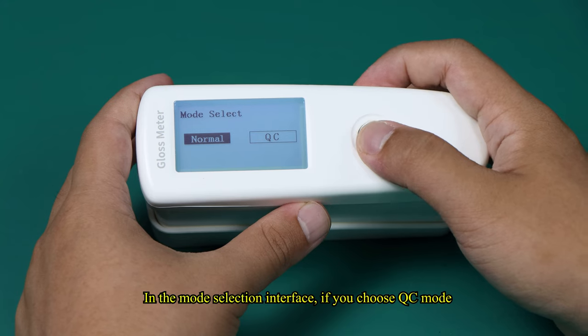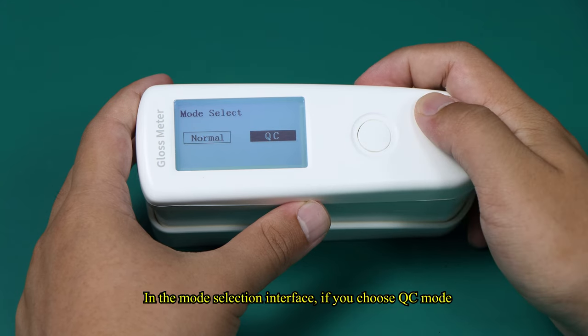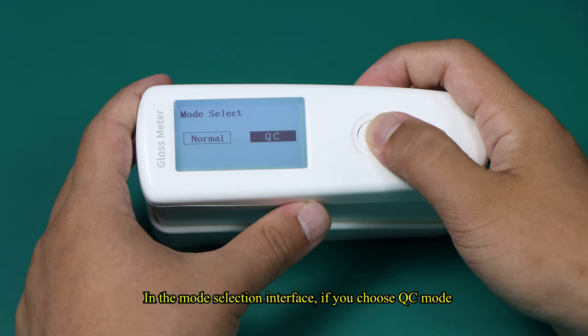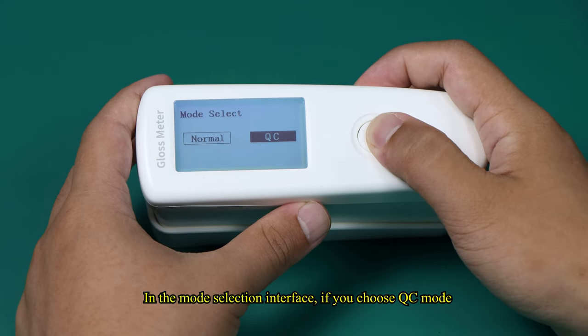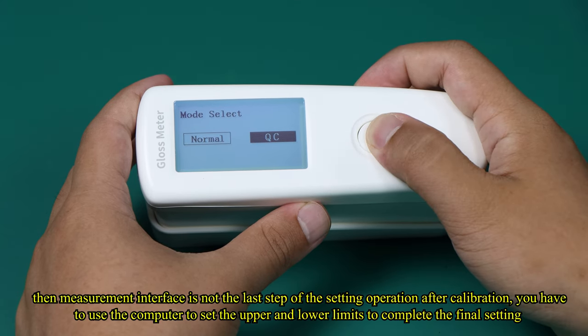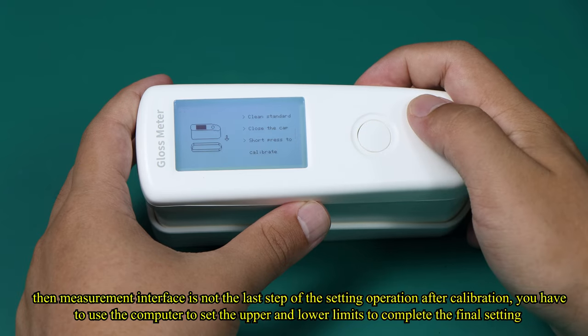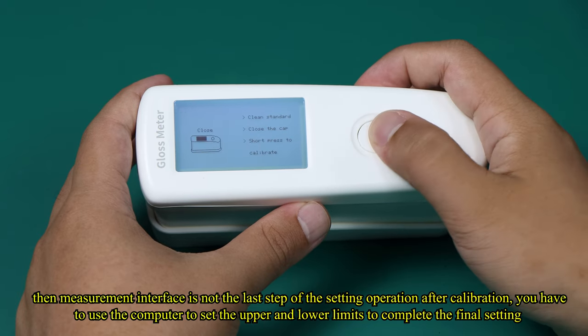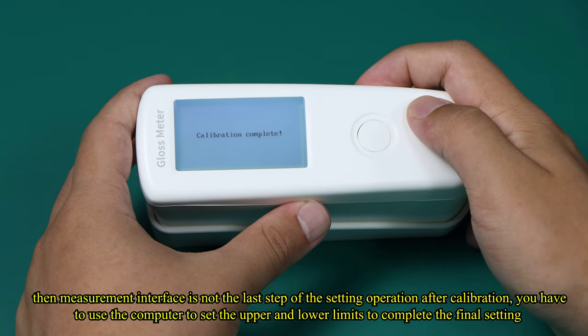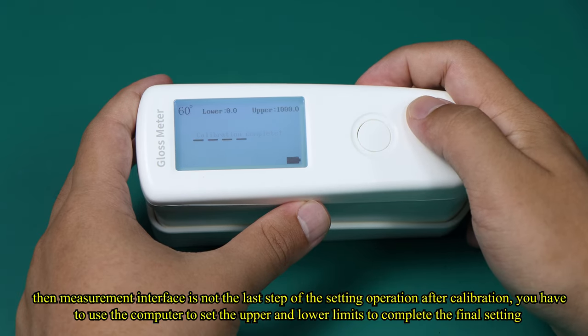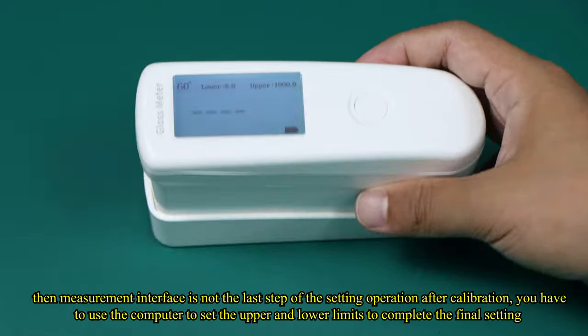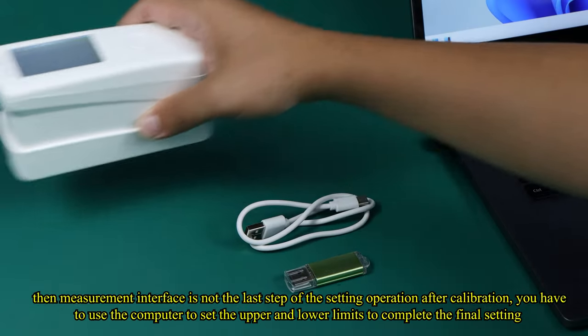In the mode selection interface, if you choose QC mode, then measurement interface is not the last step of the setting operation after calibration. You have to use the computer to set the upper and lower limits to complete the final setting.